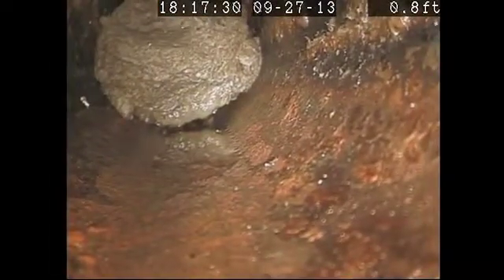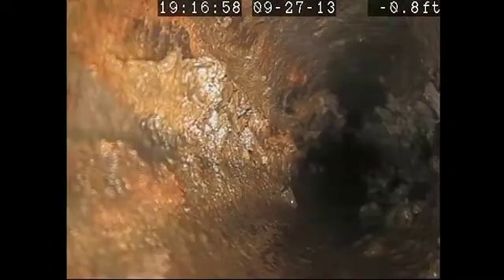The outlet should be no further than 5 to 6 feet from the stack. This will reduce the opportunity for blockages. Refrain from using 90-degree bends, but if it is absolutely necessary, ensure these are wide swept bends.